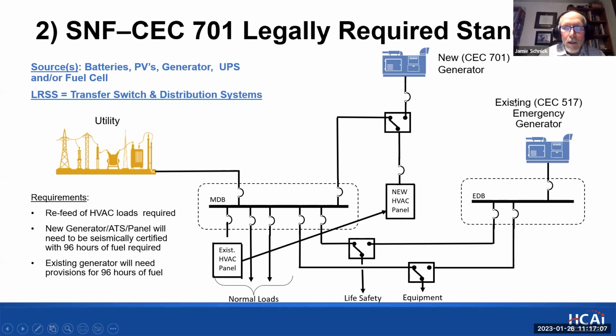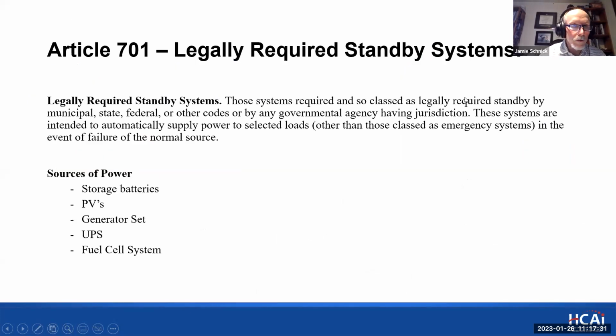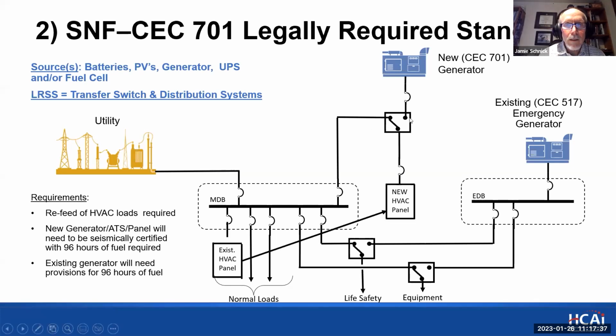Diagrammatically, what this looks like, this existing generator would remain in place. And as I said initially, this emergency system that includes the generator, the distribution board, the transfer switch, all remain in place. And independent of that, a new generator or set of batteries or other that we listed before, storage batteries, PVs, generator set, UPS, fuel cell, could be introduced to the system and connected via a transfer switch. And then a new panel introduced into the distribution system. And again, here we go ahead and transfer the existing air conditioning loads to the new panel.